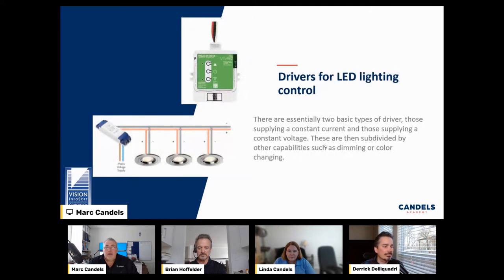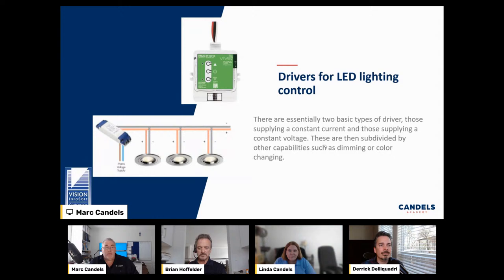Beyond low voltage lighting, you'll need a driver to control them. Instead of running 120 or 277 volts to the lights, you can use power over Ethernet — run Cat5 cable and daisy chain fixtures, controlled through drivers. The lighting control panel sends a data cable back to those drivers. Maybe 110 volts feeds the power pack of the driver and then low voltage goes out and daisy chains all the lights. Pay attention to the riser because every system operates slightly differently — don't assume.